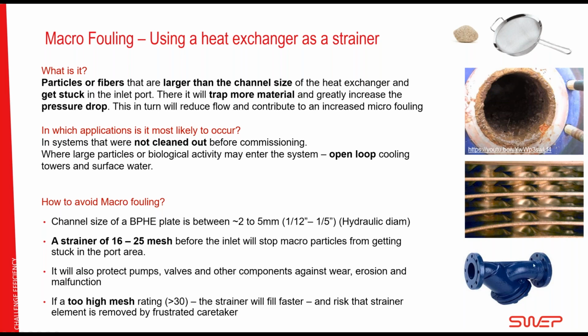In that way, the particles end up in the strainer before the heat exchanger, so you don't get stuff inside the heat exchanger. And I would say that by using a strainer, you're not only protecting the heat exchanger, but also the pumps, the valves, and other components against wear, erosion, or any kind of malfunction due to external particles. I would also like to issue a warning about using too high a mesh rating. More is not always better. If you start to use a mesh that is even higher than 25, say 30 or 40, that means they will stop smaller and smaller particles.